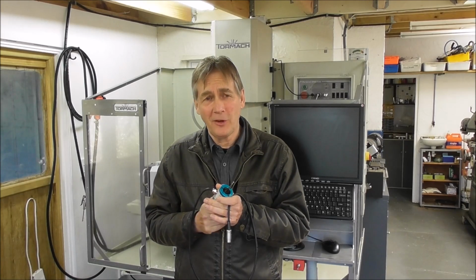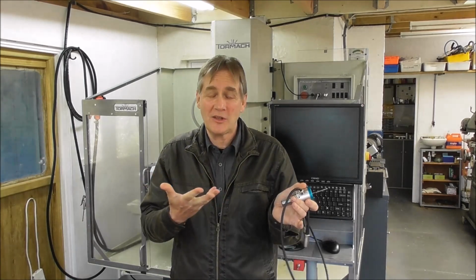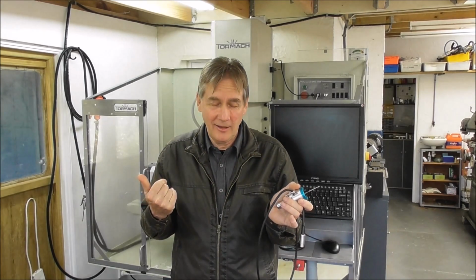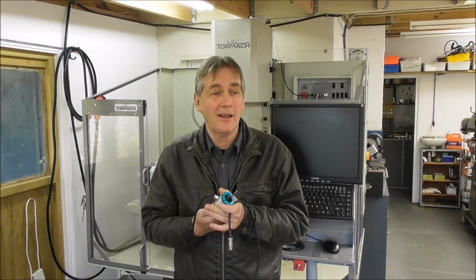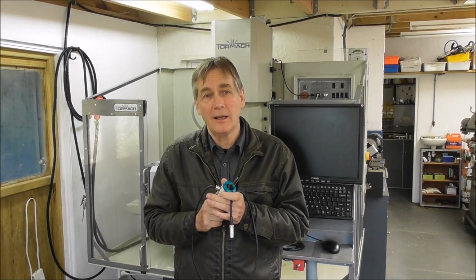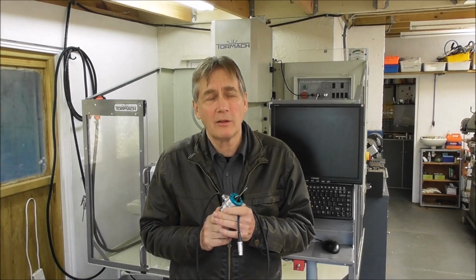It's an intermittent fault, so I've got to run it for hundreds of cycles before it shows up again, and it's really difficult to understand. So I need to take my time now and find out whether the other probes will over time develop the same fault, or whether it's an isolated fault that's very rare and unlikely to be a problem long term.